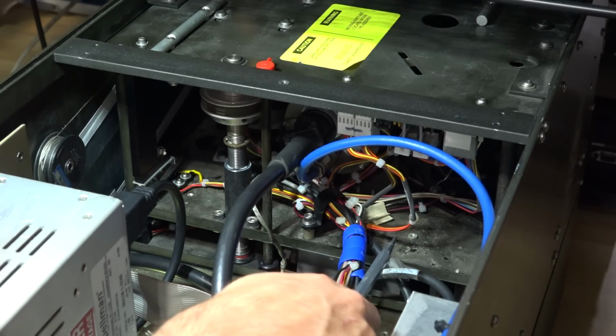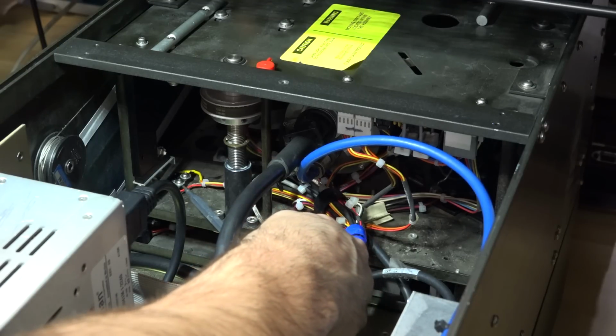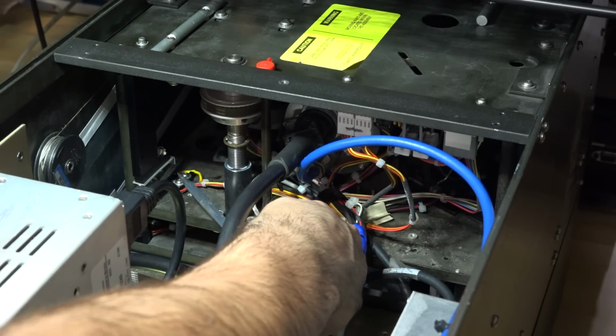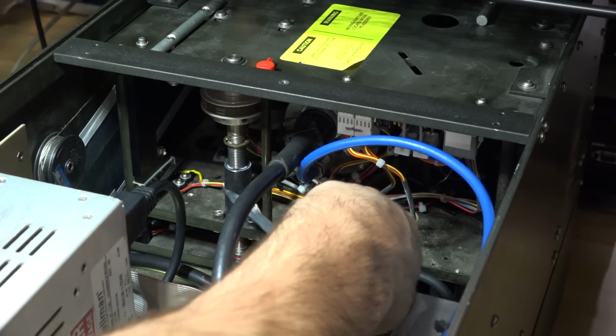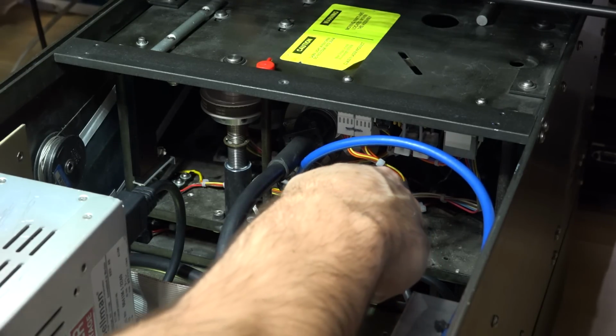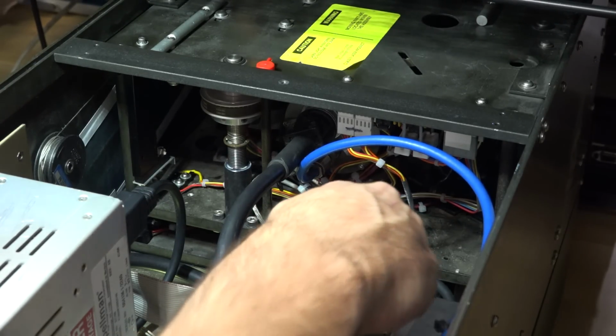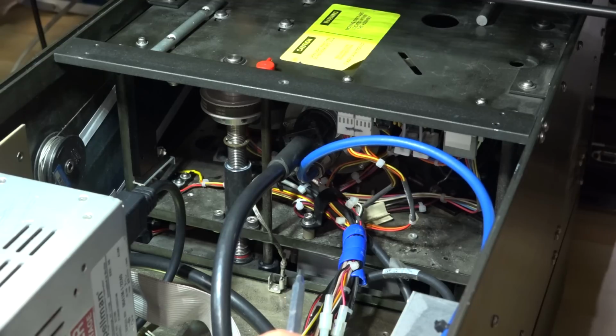It's obviously supposed to detect that it has reached a limit, because it's got these optical detectors in there, and this piece of metal enters in the middle, blocks the beam, and it knows that it has reached, for example, the top. There's also an equivalent one just underneath it at the bottom that you can't see because the stage is at the bottom right now, and it's supposed to detect the bottom limit, but neither of those were working.